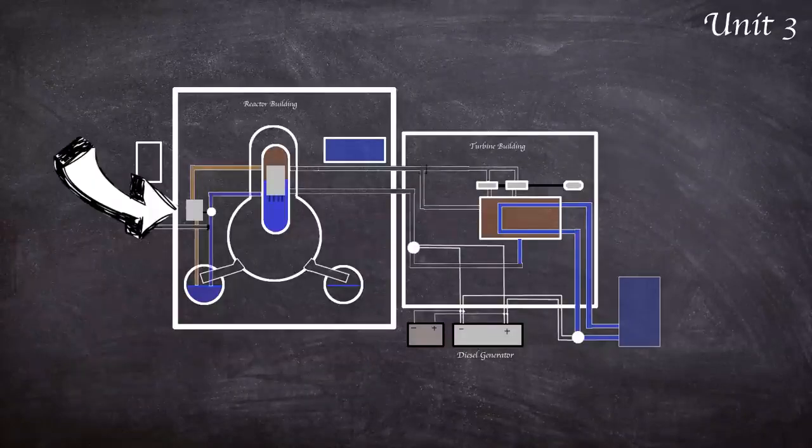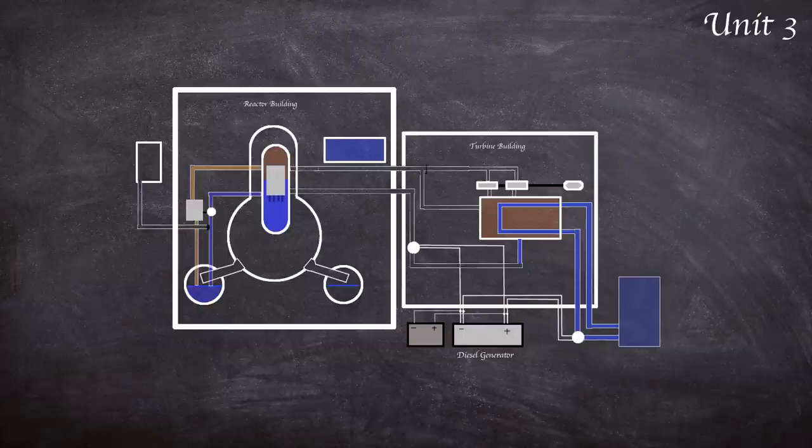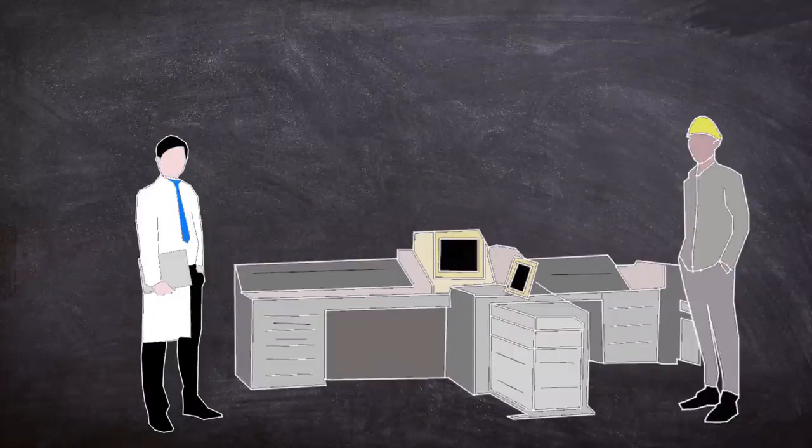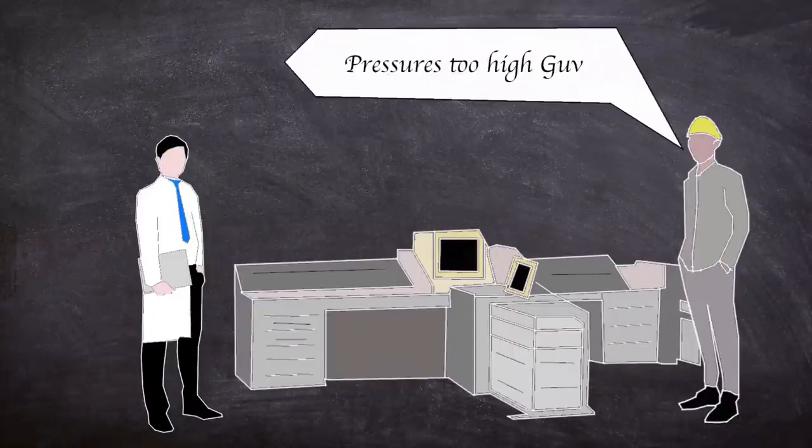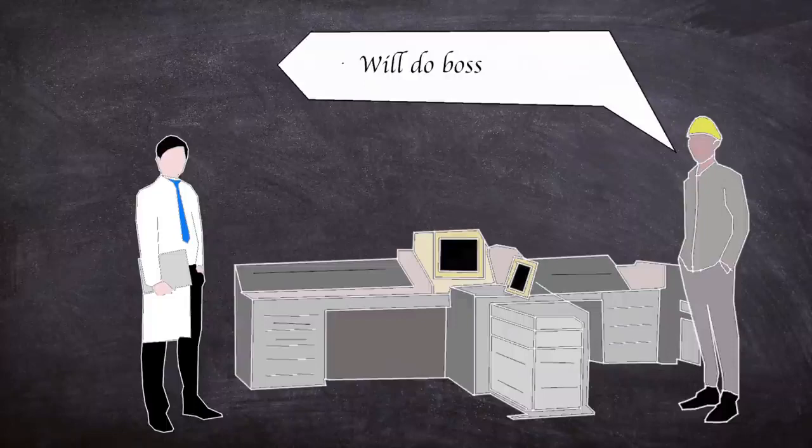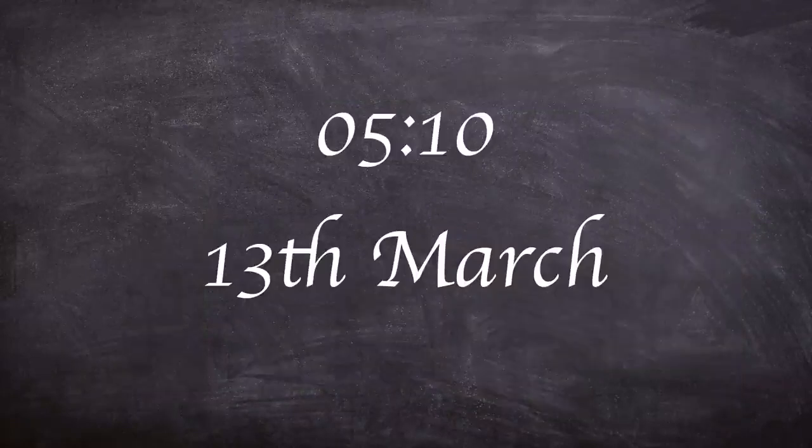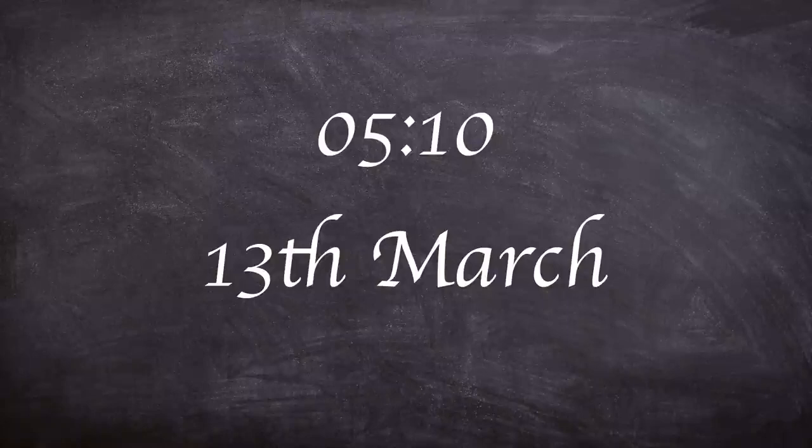Fearing the turbine-driven high pressure cooling system would fail with lowering steam, unit 3 was planned to be hooked up to an external water pumping source. To facilitate this, the high pressure system needed to be switched off for valves to be opened. The valves could not be opened. Whilst operators struggled for 45 minutes, pressure within the reactor rose, disallowing the external water pumping option. Painting themselves into a corner, operators attempted and failed to restart the high pressure system, essentially leaving unit 3 with no cooling system at all.